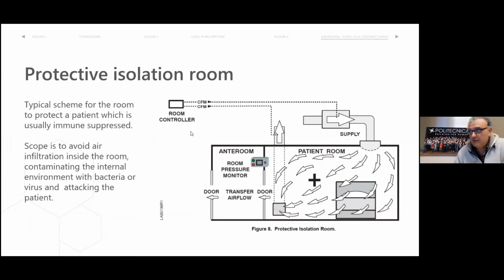This is the protective isolation room where the patient room is at over pressure, let's say, as usual, +5 Pascal. The anteroom in this case is neutral, but it is not always the same way because there are some different experiences among the various hospital staff. However, the patient room is absolutely at higher pressure. The supply is made on the side far from the door because we have to protect the patient from the bacteria and viruses that can enter from the door. So the direction of the flow is to be made from the patient bed to the door. And here there is extraction.